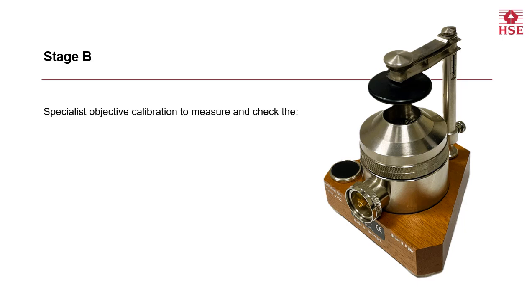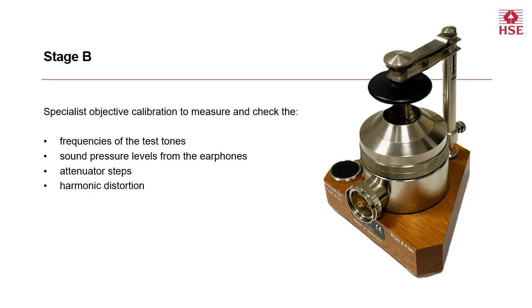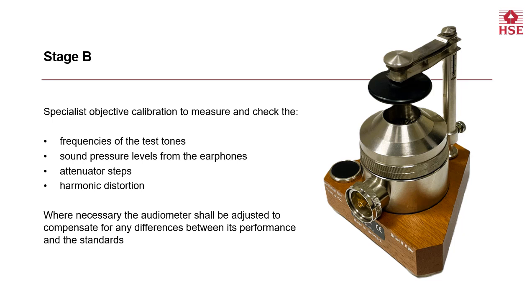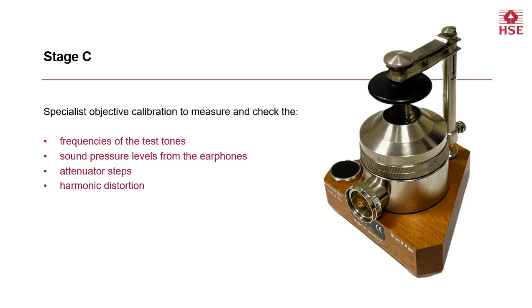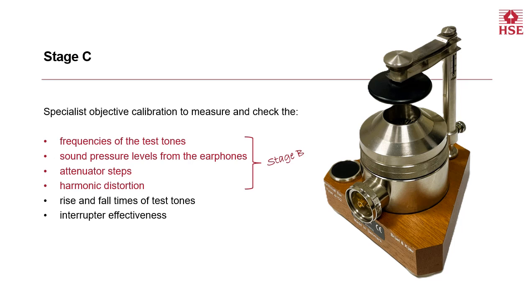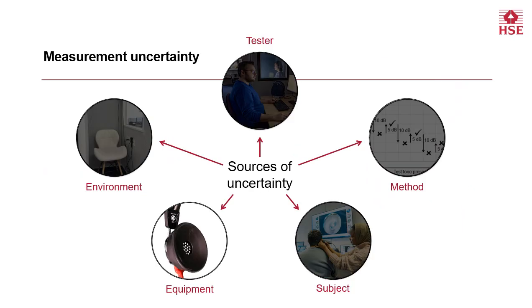Stage B involves specialist objective calibration to check the frequencies of the test tones, the sound pressure levels from the earphones, the attenuator steps, and harmonic distortion. During this process, the audiometer may be adjusted to compensate for any differences between its performance and the standards. Stage C calibration includes the checks performed in Stage B, plus the additional checks of the rise and fall times of the test tones, interrupter effectiveness, and crosstalk between transducers and channels. We have now considered how to minimize measurement uncertainty by controlling the test environment and by ensuring that the equipment we are using conforms to the appropriate standards and is well maintained and calibrated.